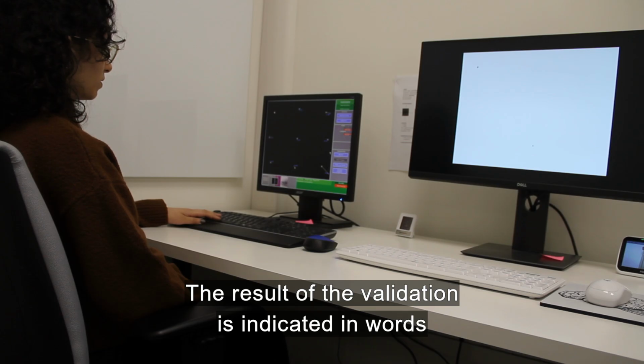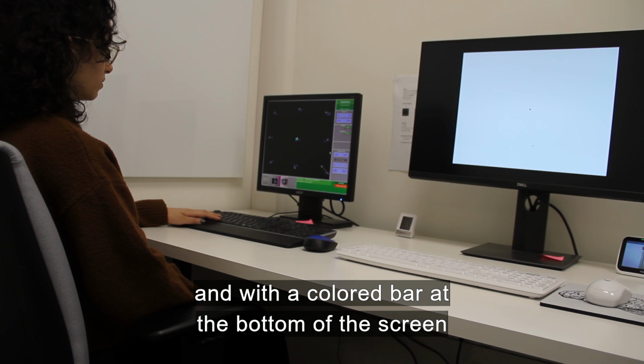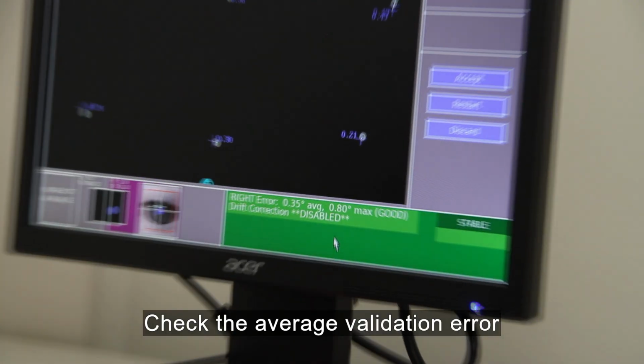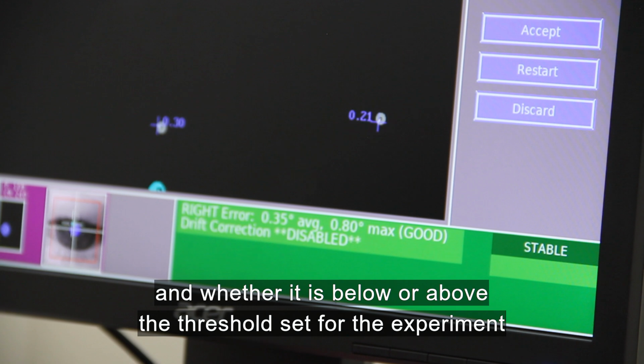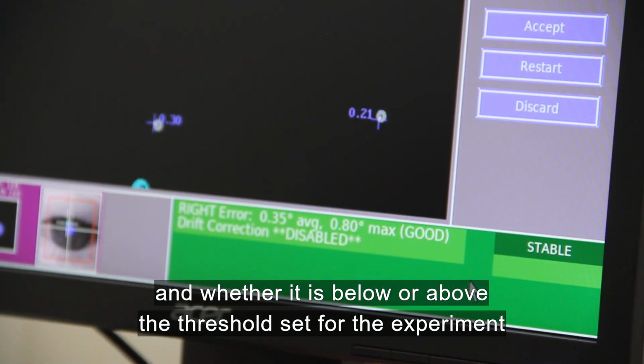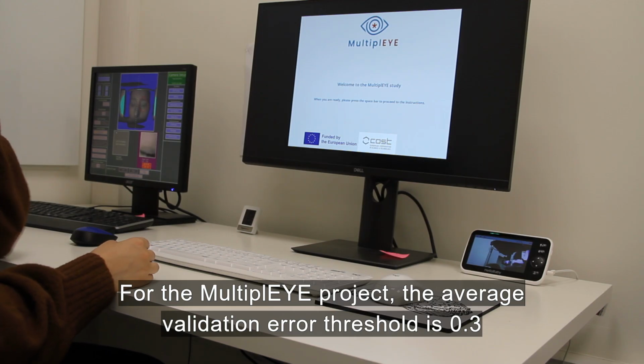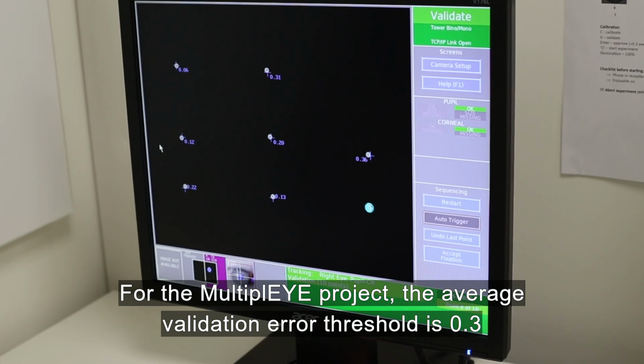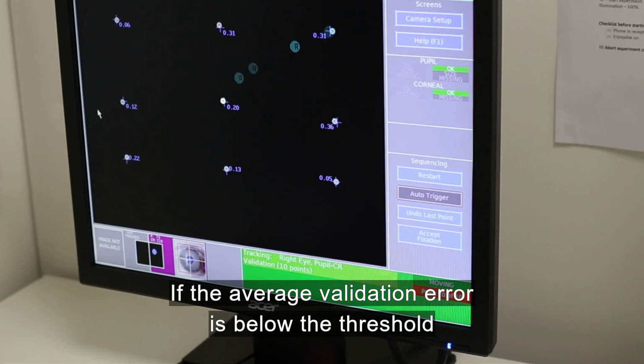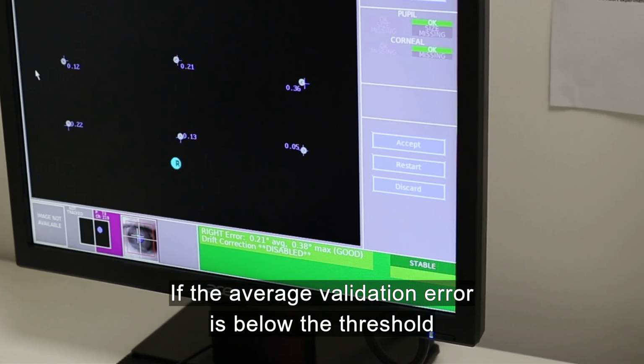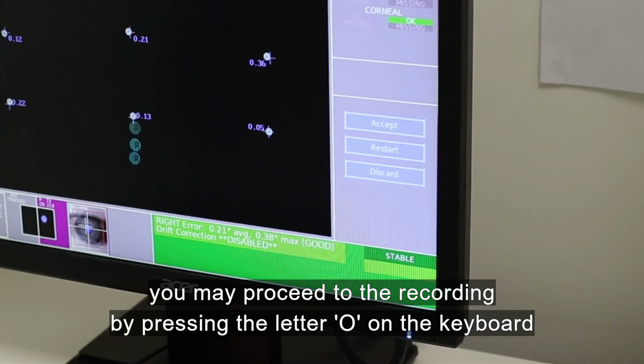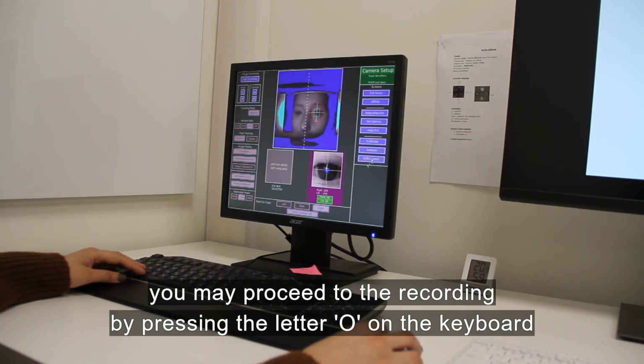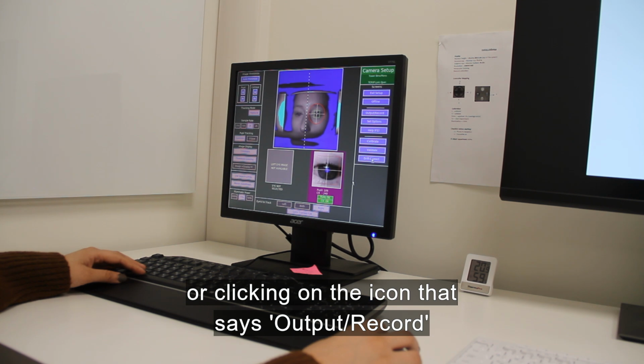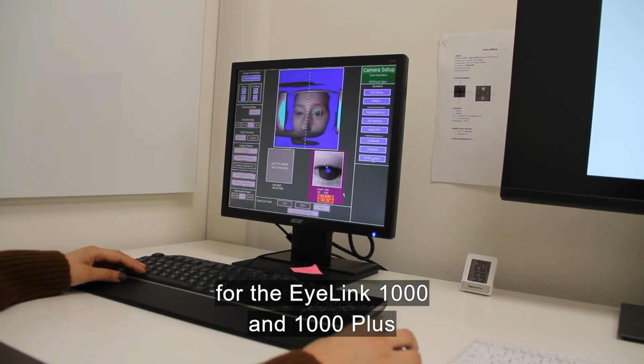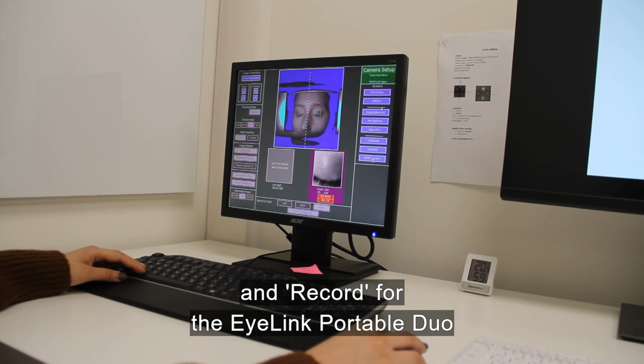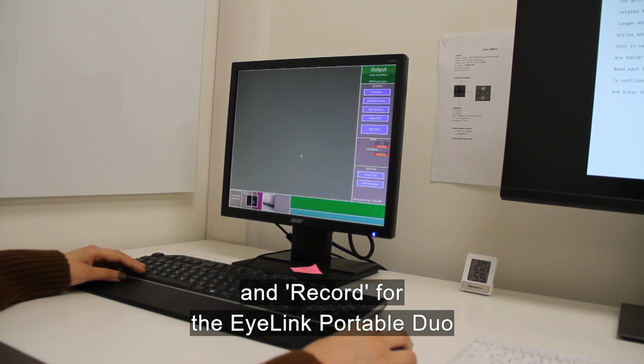The result of the validation is indicated in words and with a coloured bar at the bottom of the screen. Check the average validation error and whether it is below or above the threshold set for the experiment. For the MultiplEYE project, the average validation error threshold is 0.3. If the average validation error is below the threshold, you may proceed to the recording by pressing the letter O on the keyboard or clicking on the icon that says output/record for the EyeLink 1000 and 1000 Plus and record for the EyeLink Portable Duo.